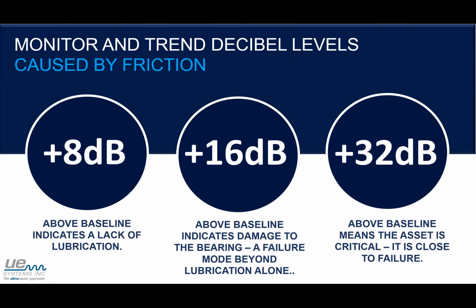It comes out of the ISO standard in terms of what we do: we set a baseline. These baselines, we could have a whole webinar on alone, how we set them, because the reality is what we say is you set a baseline on a healthy, well-lubricated bearing.